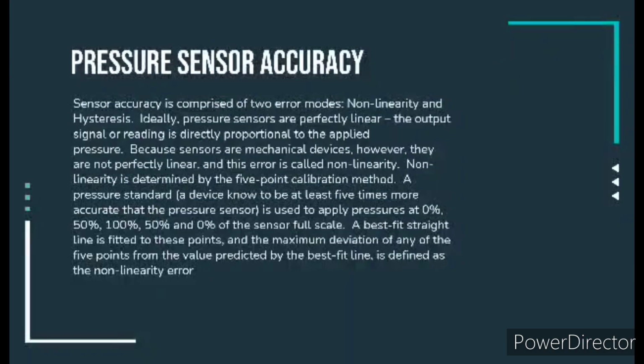Pressure sensor accuracy. Sensor accuracy is comprised of two error modes, nonlinearity and hysteresis. Ideally, pressure sensors are perfectly linear. The output signal or reading is directly proportional to the applied pressure. Because sensors are mechanical devices, however, they are not perfectly linear, and this error is called nonlinearity. Nonlinearity is determined by the 5-point calibration method.